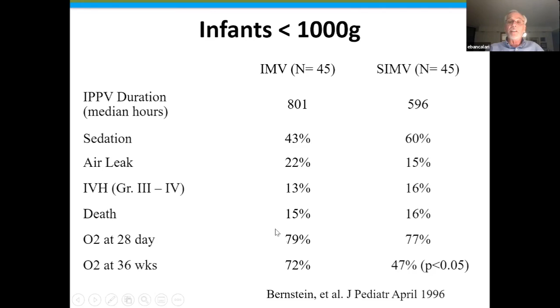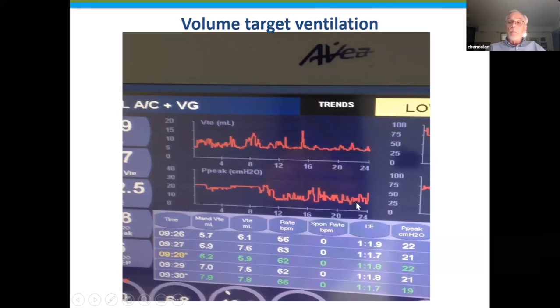The other mechanical ventilation strategy that has become much more frequently used because of the possibility of reducing BPD is volume-targeted ventilation. When we are using pressure-limited ventilation, we are giving the same pressure with each breath. If we switch our patients to volume-targeted ventilation, we are essentially giving the responsibility for adjusting the peak inspiratory pressure to the algorithm included in the ventilator, and therefore the peak inspiratory pressure will be lower as long as the baby gets the tidal volume that we set the ventilator to deliver to that patient. So usually what you see is more consistent tidal volumes and lower peak inspiratory pressures and lower mean airway pressures.